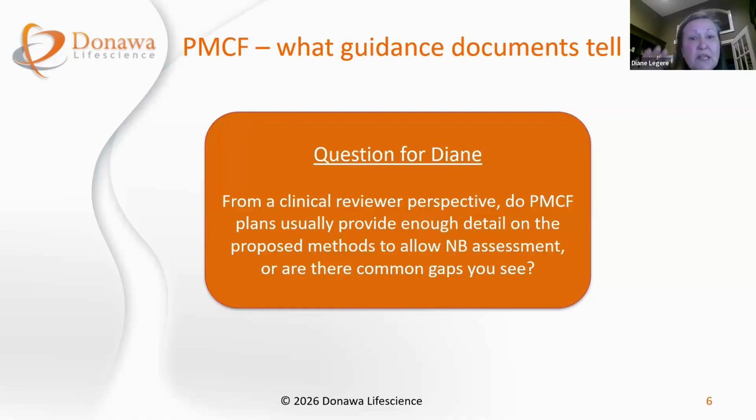You alluded to the general things, and I think there's still confusion that PMCF is part of the PMS plan. So anything that's already listed in Annex 3, a PMS plan should have the things that you mentioned: spontaneous feedback, complaints, literature. Those are general. You have to go beyond that and create specific activities like the things that you listed already. So those are the common gaps: timeliness, and specific methods for lower class devices. Thank you very much.